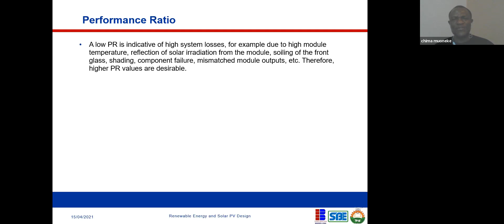In contrast, performance ratio is also used as a common reference value in the planning stage of a PV system. So just to help you during your design stage, if you're designing a solar PV system, theoretically, you can assume a certain performance ratio, because you can't just take 100% performance ratio. It is not ideal, it's not possible. So it also helps us when we are doing our design to estimate certain losses that we expect from the system. So for example, a PR of 0.75 to 0.8 is used for a grid connected PV plant. If you're designing a grid connected PV plant, you can use 0.75 to 0.8, meaning that if the solar panel can give you 100 units of energy, 20 or 25 is going to get lost. You're only going to get 75 or 80. That's what it means.